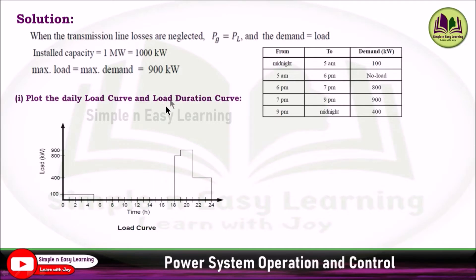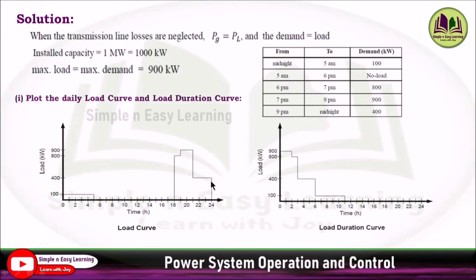For the load duration curve, assemble this load variation in descending order. The descending order is 900, then 800, 400, then 100. So first 900 kilowatt for 2 hours, then 800 kilowatt for 1 hour, then 400 kilowatt for 3 hours, and the remaining 100 kilowatt for 5 hours. This is how you draw the load duration curve.